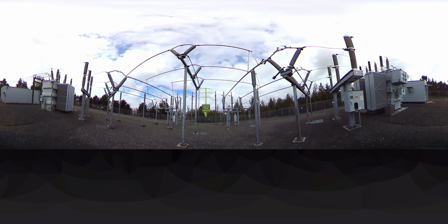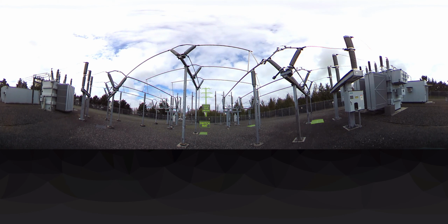We'll begin this section by covering an important safety feature of a substation. By swiveling to the right of the anchor point, you can locate switch mats at the base of any manually operated switches. These are for operators who have to manually work on the switches. When an operator stands on a switch mat, the mat ensures the operator is the same potential as the equipment they are working on, preventing them from being severely burned by current or from dying.